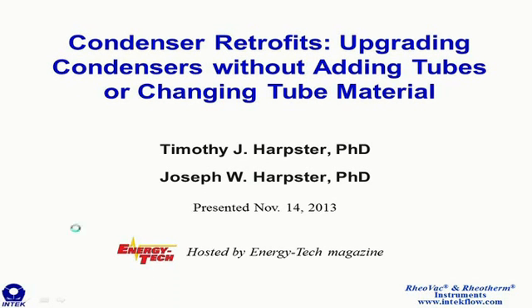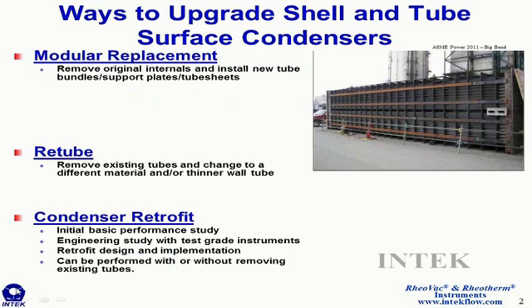The first is a modular condenser replacement. That's a process where the existing condenser tubes, support plates, and tube sheets are removed, leaving an empty condenser shell. A self-supported tube bundle module, shown here, that is fabricated in a manufacturer's shop, is shipped on site and is maneuvered into the empty shell. The module could have a new tube arrangement, more tubes, different tube OD, different tube wall thickness, and perhaps a different tube material. And depending on the design choices, you can expect a performance upgrade.